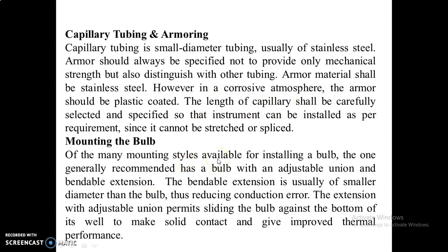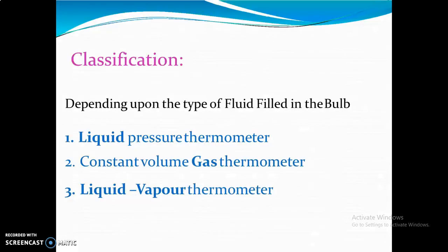Many mounting styles are available for installing the bulb. The mounting mechanism uses an adjustable union and a bendable extension. The bendable extension is usually smaller in diameter than the bulb, reducing conduction error. The extension with adjustable union permits sliding the bulb against the bottom of its well to make solid contact. Depending upon the type of fluid filled in the bulb, there are three types: liquid pressure, constant volume gas thermometer, and liquid vapor thermometer.